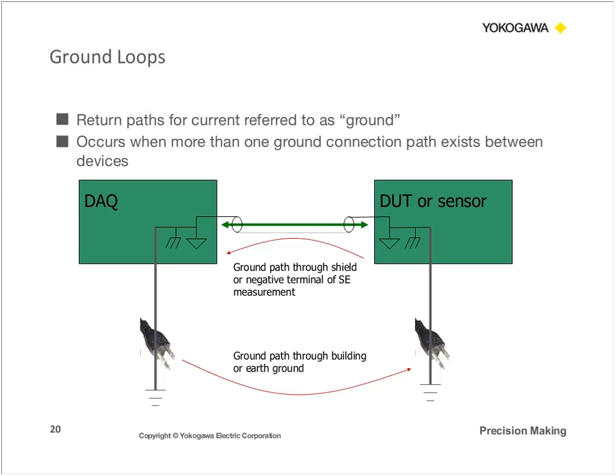Ground from the receptacle at different locations can have different voltage potential. This means that one could be sitting at 0 volts and the ground at another receptacle at a different location in the plant could be maybe 0.5 volts or even 1 volt. So there's a potential for voltage difference, and in this example that I've put here, let's say you have your data acquisition system connected to one receptacle in one room, and let's say you have a test environment in a separate room, and that's connected to a different power mains, okay? And let's say you're running cabling through the two systems.